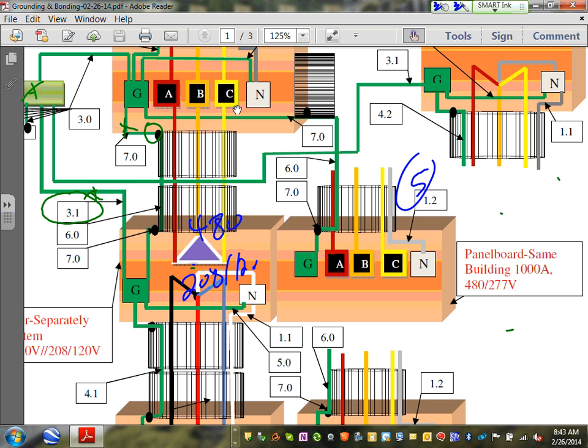So how do we ground and bond the separately derived system? Do you understand what a separately derived system is? No connection whatsoever between the primary conductors to the transformer and the secondary conductors from the transformer, except through the grounding wires, which they don't count. Phases and neutrals are completely isolated. Do you see the neutral coming out and the phases here and in here? Completely isolated from each other. That's called a separately derived system.